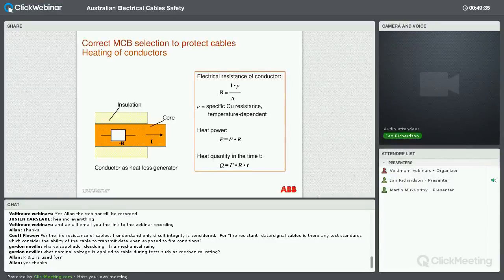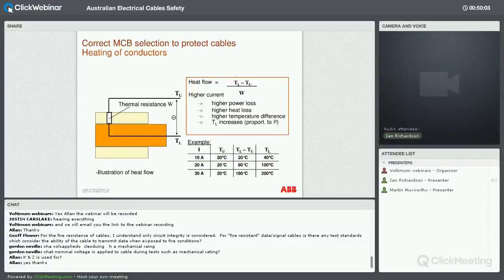So what happens with our cables passing current? As any cable or any conductor passes current, it generates heat naturally enough. There's a few formulas there about the amount of heat that might be generated. This will then affect the insulation which is surrounding the conductor, and it depends a lot on the cable design, which is Martin's area of expertise, as to what these characteristics could be. There are ways we can do further calculations, but this thermal resistance value is the way the heat is transferred through the insulation into the ambient area there. So these are considerations we have to be careful of, and the impact it can have onto what will become the life expectancy of our cable.